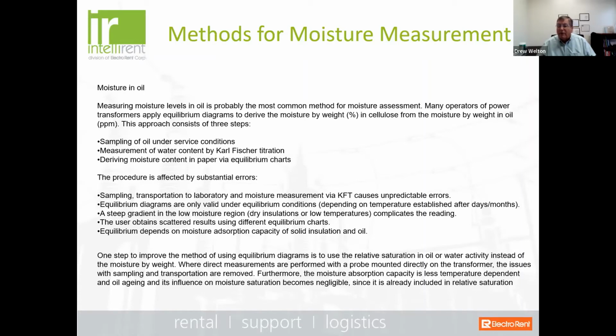So if you record the oil temperature when you take the sample, you can apply that to make a reference to what would typically be in the insulation. But there's a couple of problems with that. Number one is if your sample gets compromised and exposed to any kind of atmospheric conditions between the drawing of the sample and the laboratory analysis, it can give you unpredictable errors. The equilibrium diagrams are only valid under certain conditions, depending on the temperature of the transformer. One of the issues that you also have is that if you're recording your top oil temperature as you draw the sample through the ball valve of your transformer, that's going to cool the oil coming into play. So that could also distort your results.